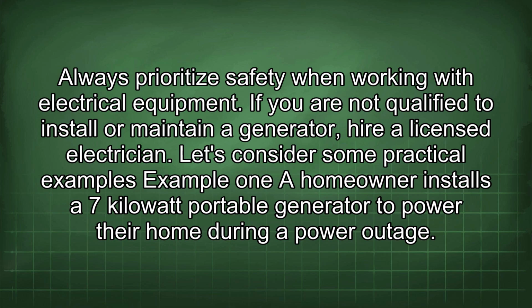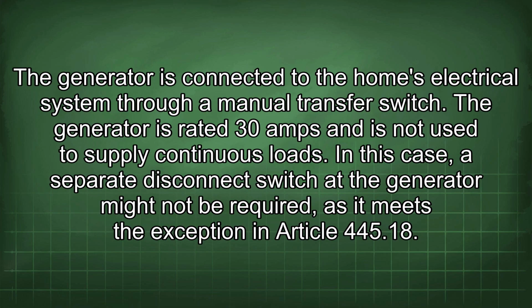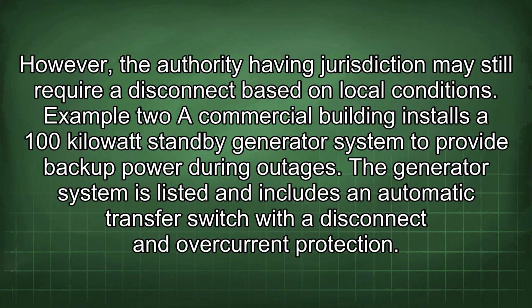Let's consider some practical examples. Example 1. A homeowner installs a 7 kilowatt portable generator to power their home during a power outage. The generator is connected to the home's electrical system through a manual transfer switch. The generator is rated 30 amps and is not used to supply continuous loads. In this case, a separate disconnect switch at the generator might not be required as it meets the exception in Article 445.18. However, the authority having jurisdiction may still require a disconnect based on local conditions.